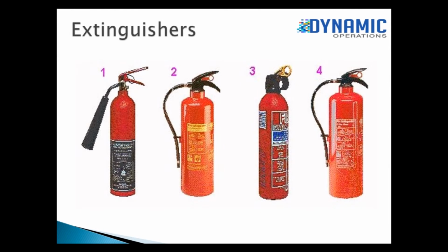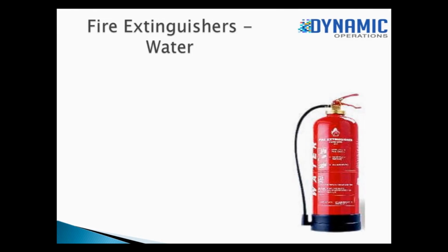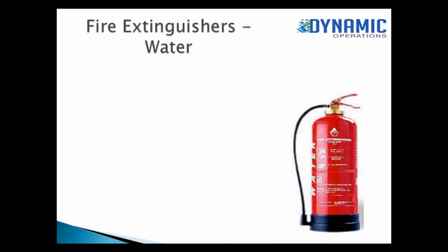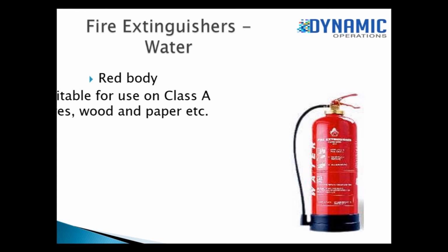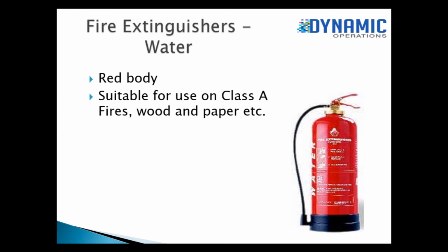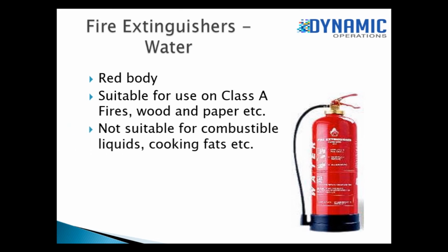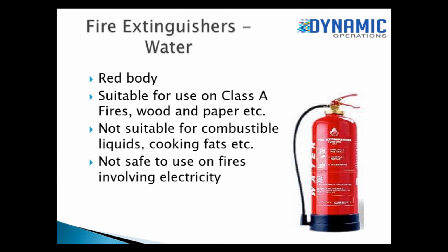Different types of fire extinguisher. Water, red body, white labelling. Suitable for use on Class A fires such as wood, paper, etc. Not suitable for combustible liquids, cooking fats. Not safe to use on fires involving electricity. And it extinguishes by cooling.